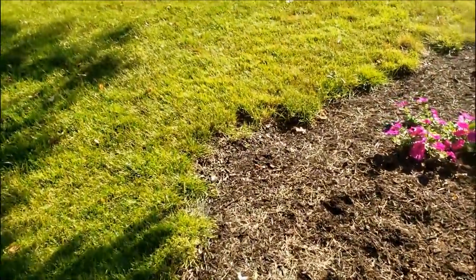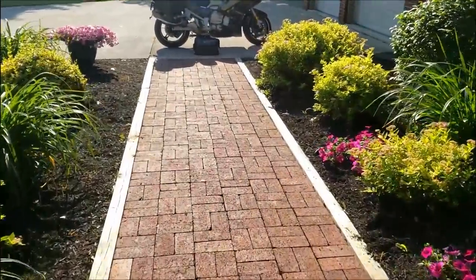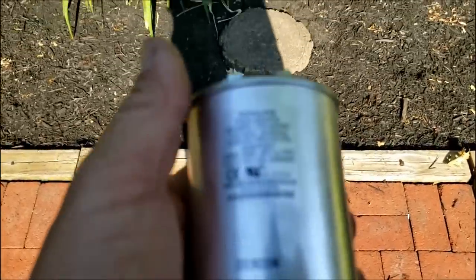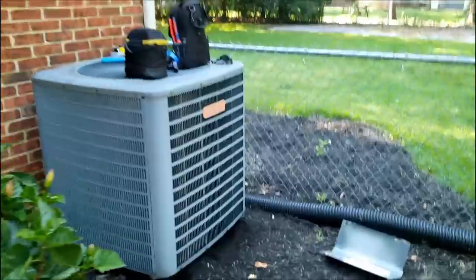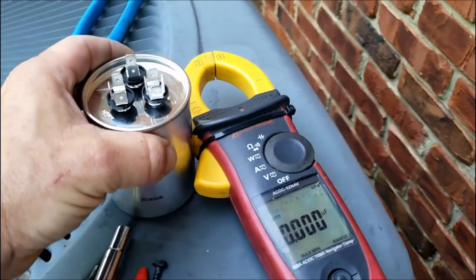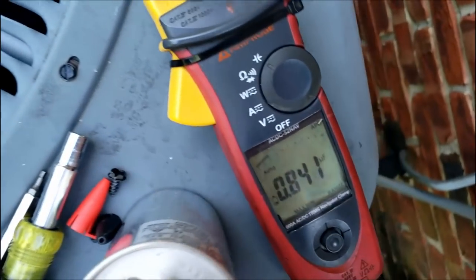This can be an easy call — figured it would be — but that's the reason I decided to do this short video, a little break from the norm. We'll go ahead and get this thing on there. I have a bad feeling though that with that coil burned up the way it is, it may have taken out his thermostat too. So like I said, collect all your clues for the problem you've got going on, and don't just do one thing and walk away. We'll double-check this one too while we're at it.